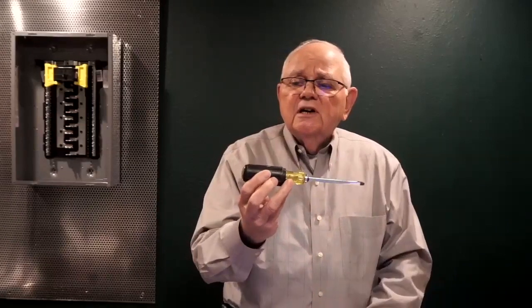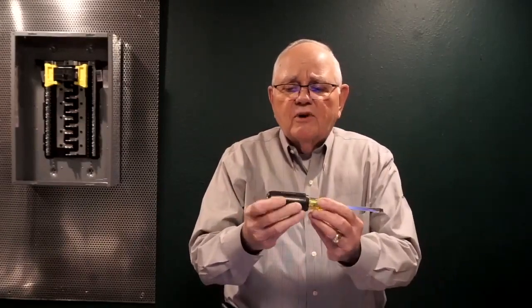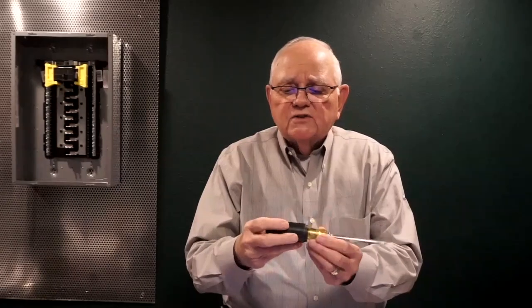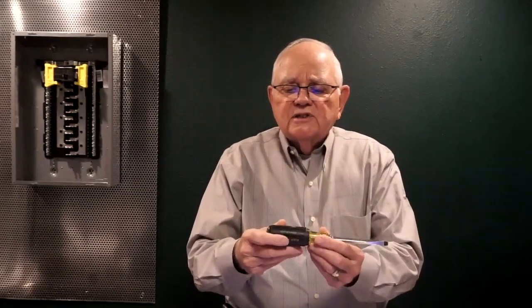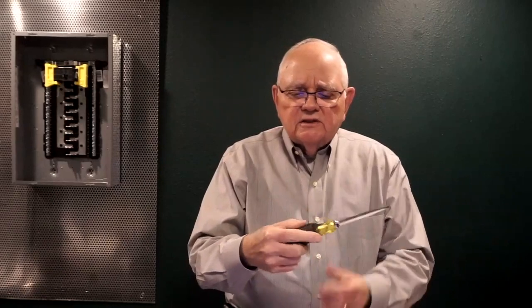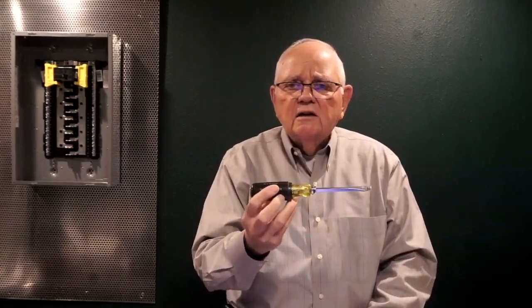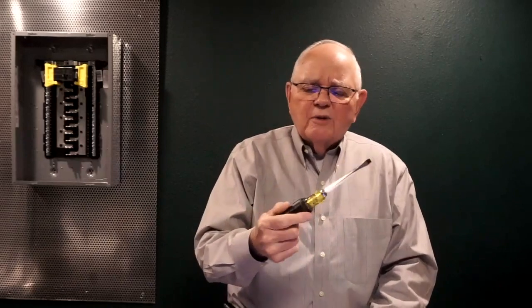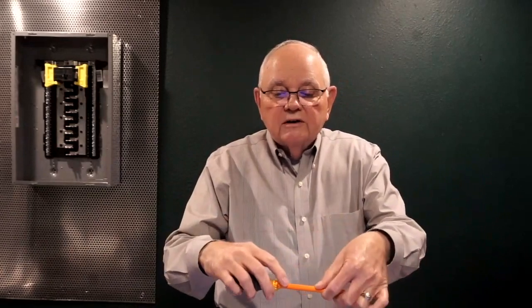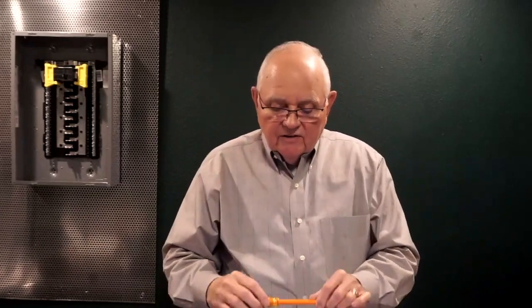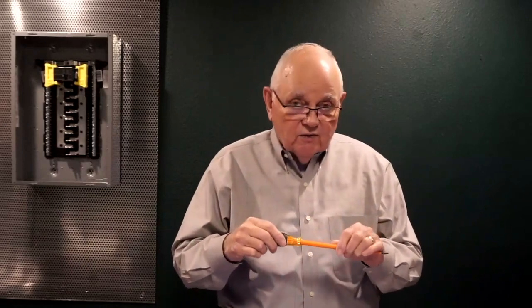Insulated tools. Let's talk a little bit about insulated tools. This screwdriver right here has a rubber handle on it, good quality screwdriver, no problems. However, it says on here it's not good for protection from electrical shock. Heck no. I mean, yeah, that's rubber and that protects me, but how much? I don't know. It's not rated. What I'm looking for on a screwdriver is something that has a double triangle on it, one triangle inside of the other. And that tells me that my tool has been tested to 1,000 volts and meets the standard for being an insulated tool.